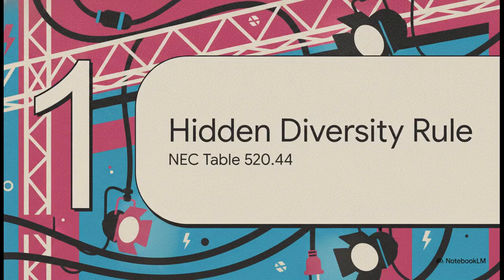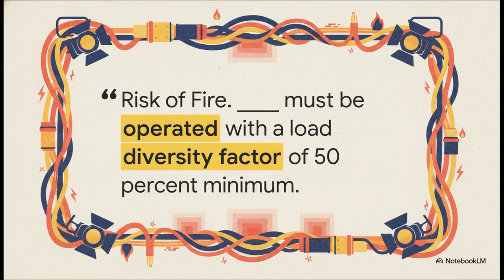Section 1. The Hidden Diversity Rule. NEC Table 520.44. Now, there's a specific UL listing warning you'll find on a lot of this gear. It reads, "Risk of fire, must be operated with a load diversity factor of 50% minimum." That blank space is usually filled with the word "border light" or "connector strip," and this points to a hidden rule buried right in NEC Table 520.44. See, because theaters use so many cables tightly bundled together, the code allows for a more generous ampacity adjustment, a 60% allowance to be exact.